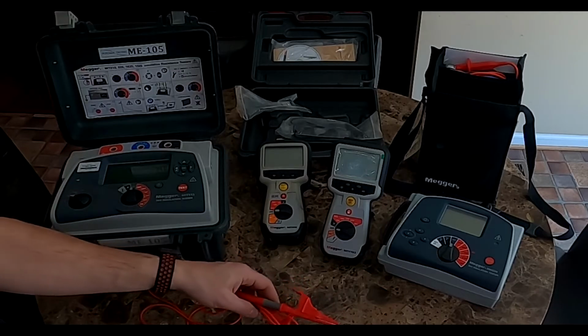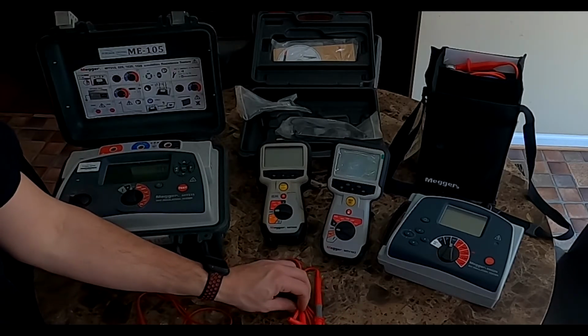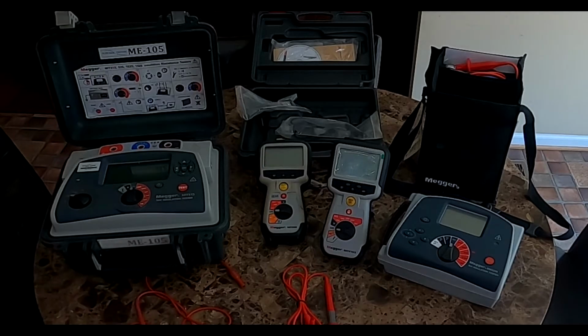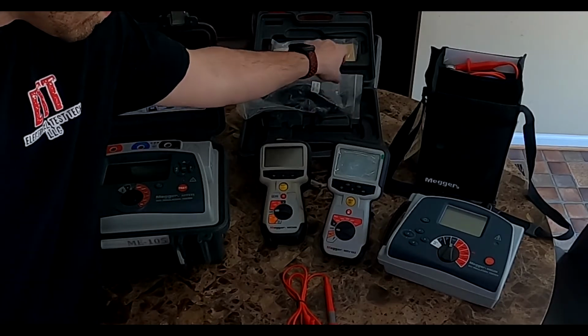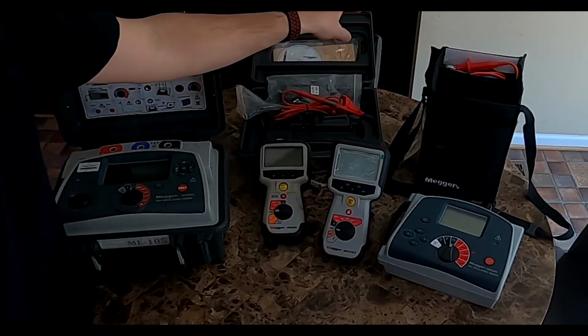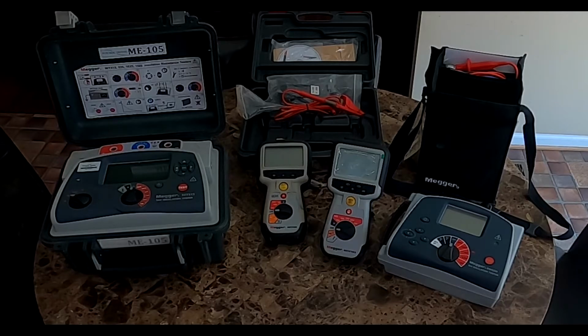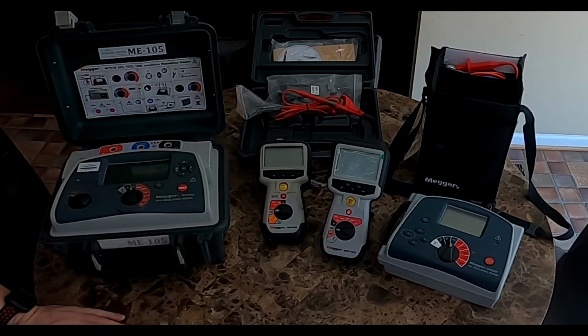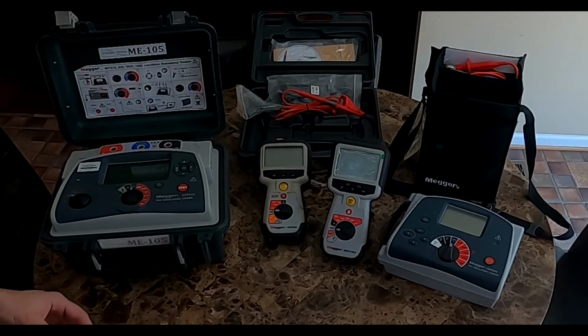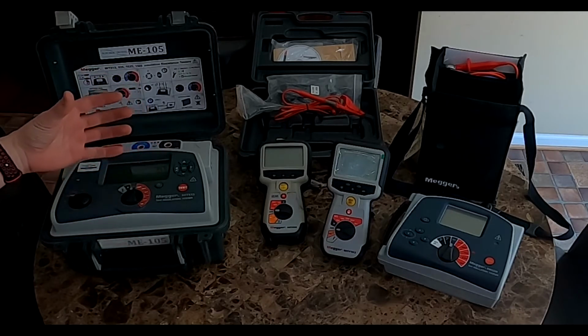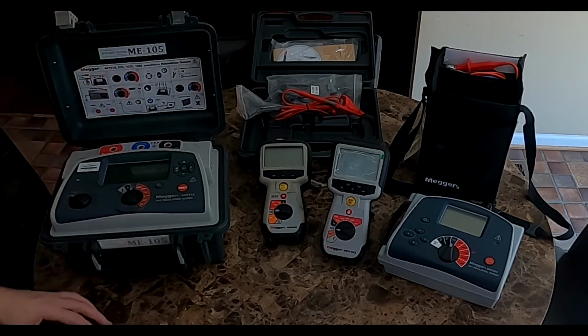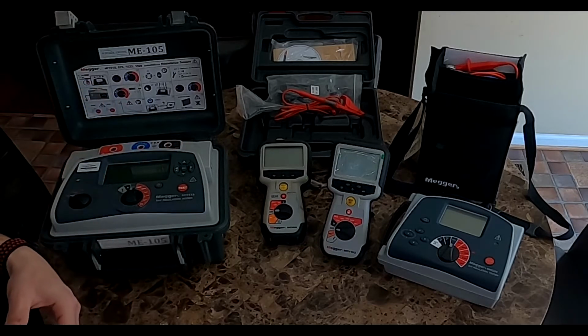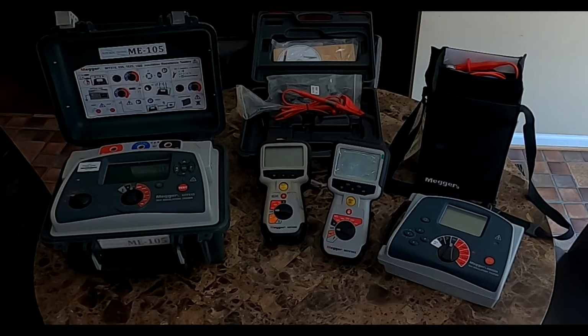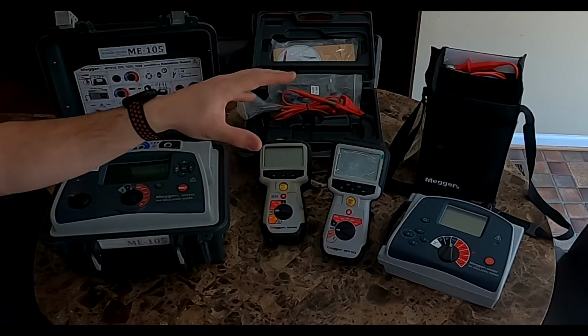But my advice would be to use the cables that come with Megger, as they're typically the silicone 1,000 volt rated cables. If you use different leads with these devices, if they're not the Megger brand or some sort of 1,000 volt or 5,000 volt rated leads, you tend to get a lot of other influences when you're testing equipment. Just you moving your hand close to the leads or having the leads laying on top of each other, you will get lower readings, or it'll cause it to be at less than 1 PI. So it's best to use the leads that come with the equipment.